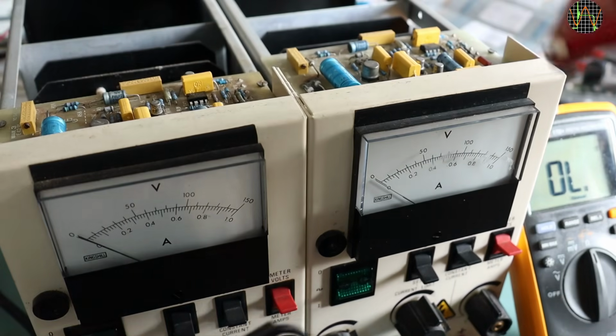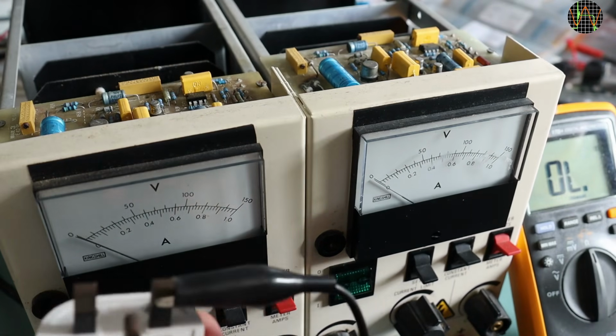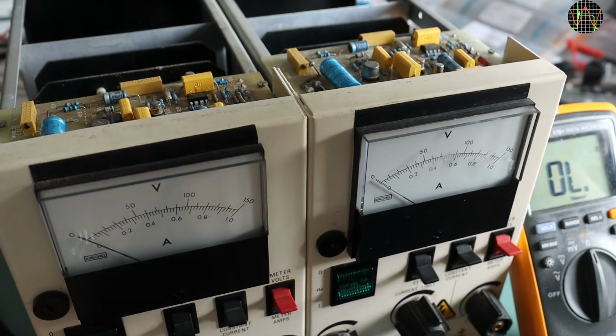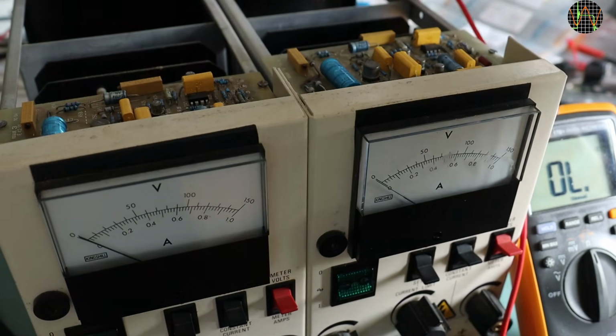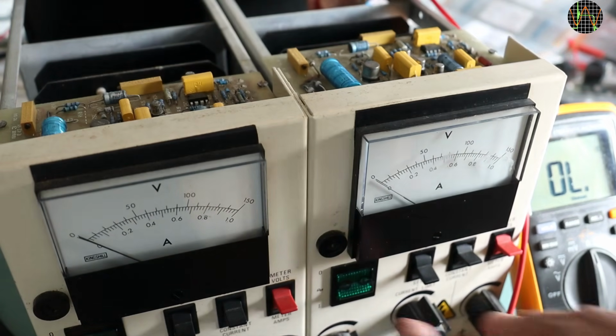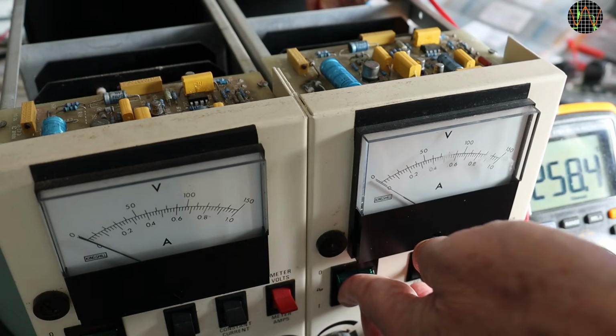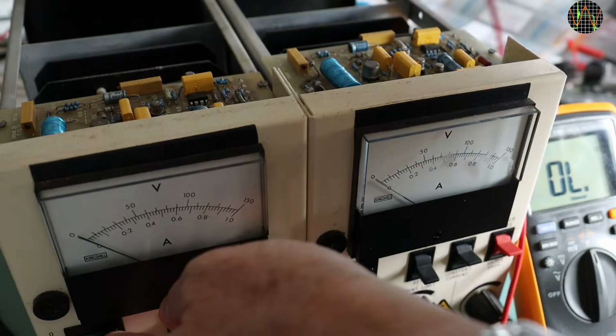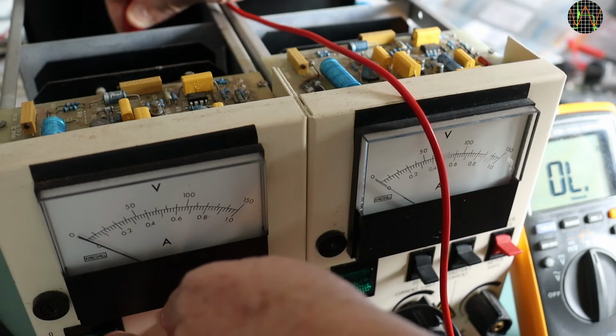The power switches are of the double pole single throw type, and connecting one lead of the multimeter to neutral, I can verify that on the working power supply, neutral reaches the transformer when the switch is turned on. On the left unit it does not.